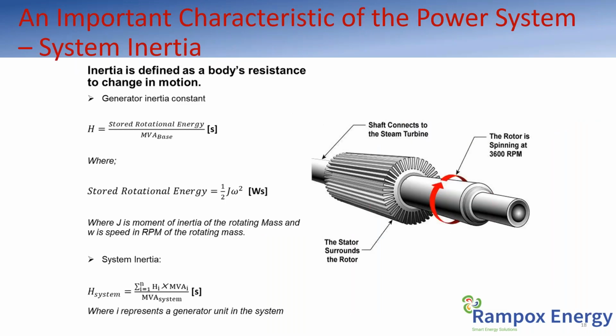And then this shows what is termed power system inertia, where basically it's just the rotational energy of all rotating machinery in the power system aggregated together, to give what is called the H constant of the system. That is, the stored rotational energy of the system divided by the MVA base of the system will give you your inertia constant of the system, and your stored rotational energy, which is half J omega squared.